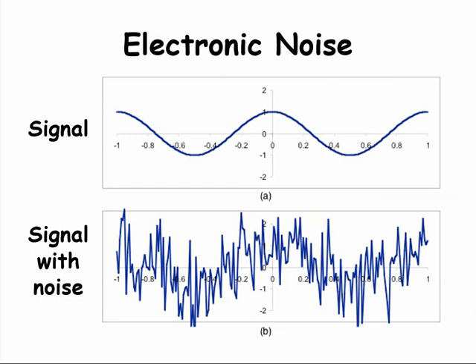We have talked about noise before. This slide tries to show how noise is part of an electronic signal, and that noise can make it difficult to find the signal. Noise can be generated or picked up from other electrical equipment in the area or power lines that are near wires connecting sensors to data acquisition equipment. It is important to understand that it is difficult to eliminate noise. So noise needs to be anticipated and managed.